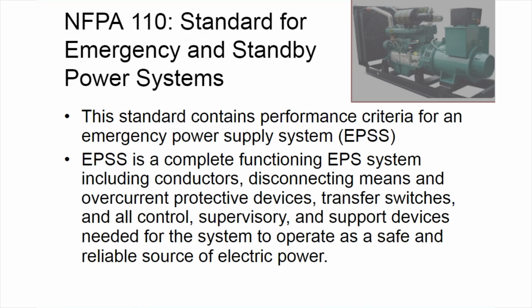The Level 1 EPSS are installed where failure of the equipment to perform could result in loss of human life or serious injuries. So basically life safety loads. Level 2 systems are installed where failure of the EPSS to perform is less critical to human life and safety. So optional loads may be mechanical equipment, that type of thing. The class defines the minimum time the EPSS must be designed to operate at its rated load without being refueled or recharged. The type defines a maximum time in seconds that an EPSS will permit the load terminals of the transfer switch to be without acceptable electrical power. So how long does it take to transfer?